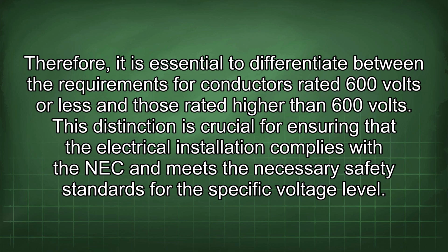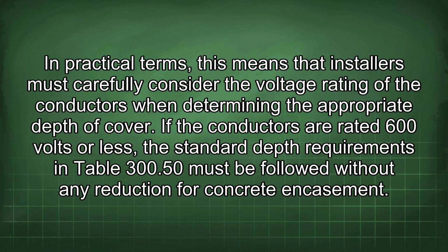This distinction is crucial for ensuring that the electrical installation complies with the NEC and meets the necessary safety standards for the specific voltage level. In practical terms, this means that installers must carefully consider the voltage rating of the conductors when determining the appropriate depth of cover. If the conductors are rated 600 volts or less, the standard depth requirements in Table 300.50 must be followed without any reduction for concrete encasement.